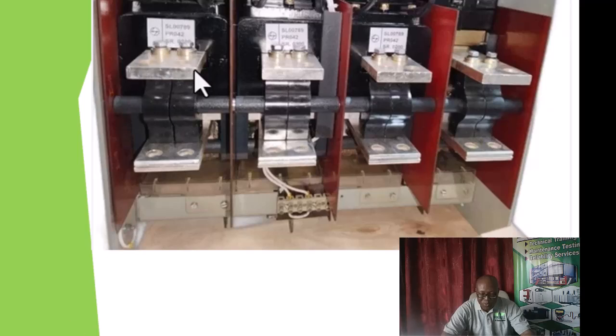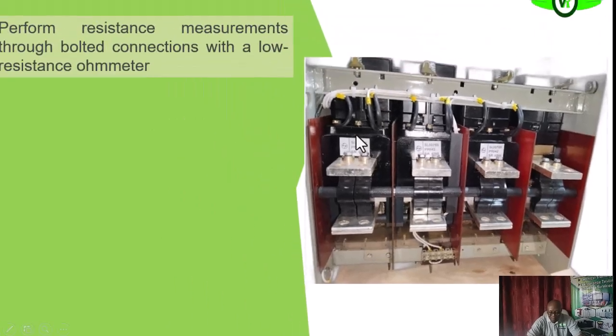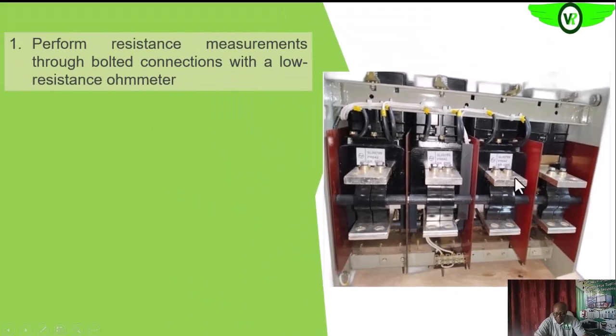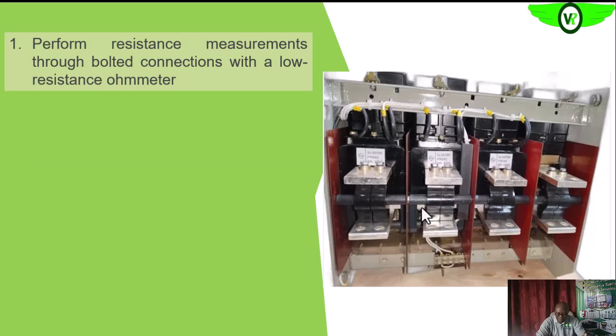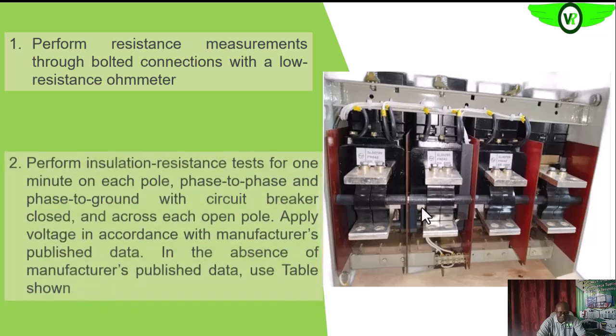What we are trying to do is to ascertain that the connection is firm. But all of these bars, remember, are only connected when you are racking them in. So we may not have access to them, but we want to be sure that they are very clean. If we can access the input cable and the output cable, we want to check the resistance at those connection points.